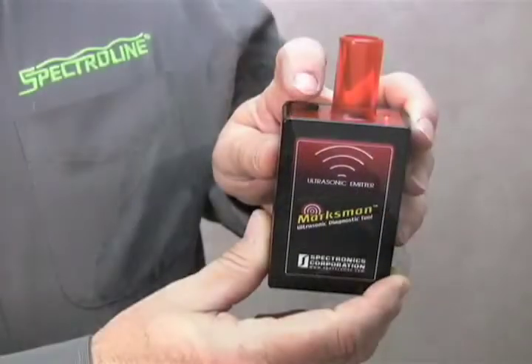Earlier I mentioned to you that the Marksman is great for diagnosing pressurized leaks. But what about those pesky air and water leaks in non-pressurized enclosures like holding tanks and ductwork? That's where the ultrasonic emitter comes in. In a nutshell, the emitter simulates a pressurized leak by generating a beeping sound optimized to the frequency range of the receiver. Just turn on this little switch, place the emitter in the enclosure, and walk around the exterior by sweeping the suspect areas with the receiver. The exact location of the leak will be immediately revealed by an increase in the intensity of the beeping sound from the headphones.